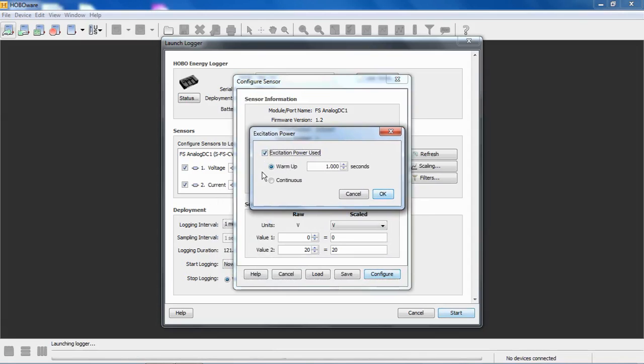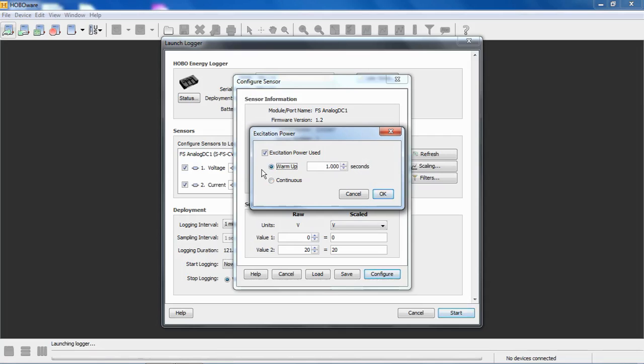HoboWare, or this logger, supports either continuous power, so continuous 12 volts. As soon as you turn it on, the power is turned on to the sensor, or we support a programmable warm-up time. The way the warm-up time works is in this configuration, you can see we have a one-second warm-up time. One second before the logging interval happens, the sensor will be powered. Then the logging interval happens, the measurement is taken, it's recorded in a data file, and then that power is turned off again until one second before the next interval. This considerably saves on battery power if you're running off battery.